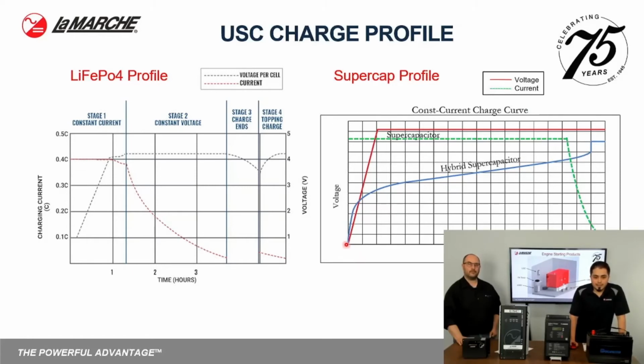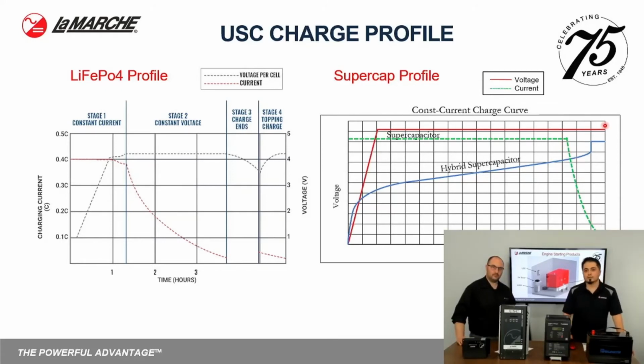Going into a supercap profile here on the right side, you can see a constant current again, so you have almost a similar stage 1 as you would with the lithium iron phosphate battery, where you get that constant current, as you see the dotted green line, until you get to a constant voltage at a certain point. You would then, at the end of this stage, drop down into a stage where your current again would taper off, and you would have just a standing float current to maintain your supercap.